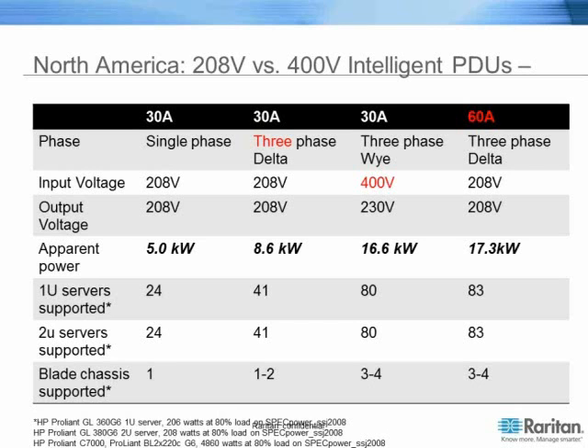This is 30 amp 3-phase Y and 60 amp 3-phase delta. On the 3-phase Y, we're bringing in 400 volt. If you look at the numbers, 16.6 versus 17.3, not quite the same. However, it's really, really close to the amount of power we can bring in.